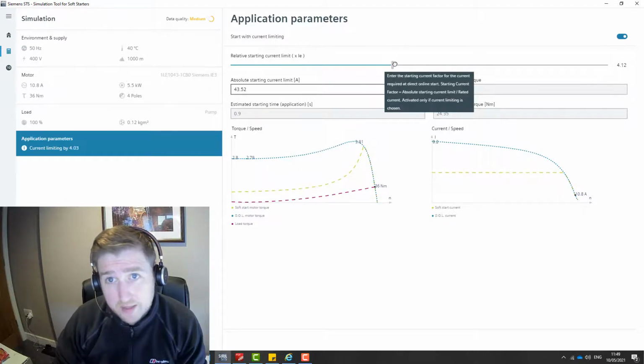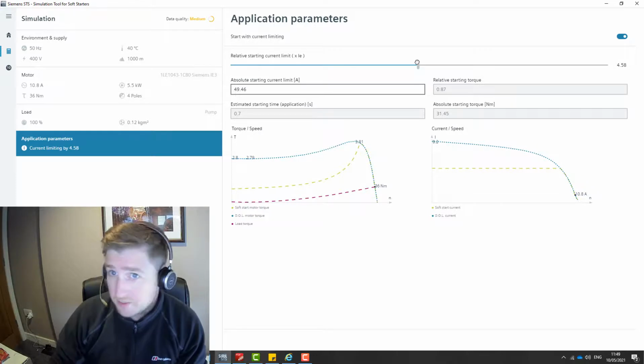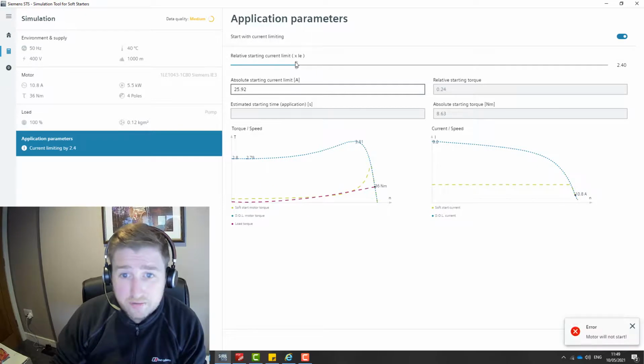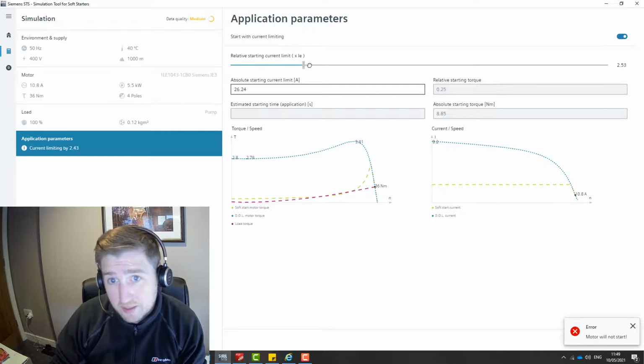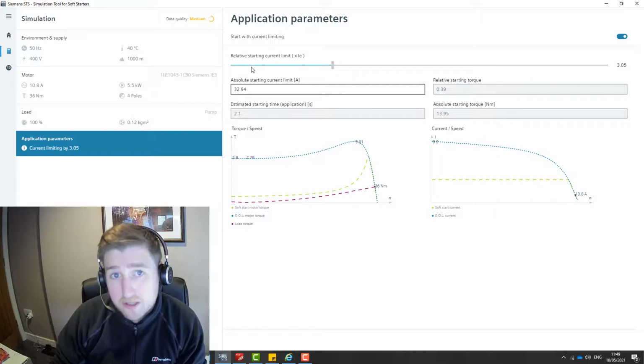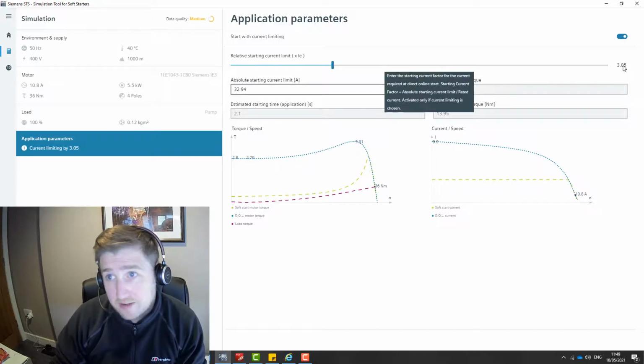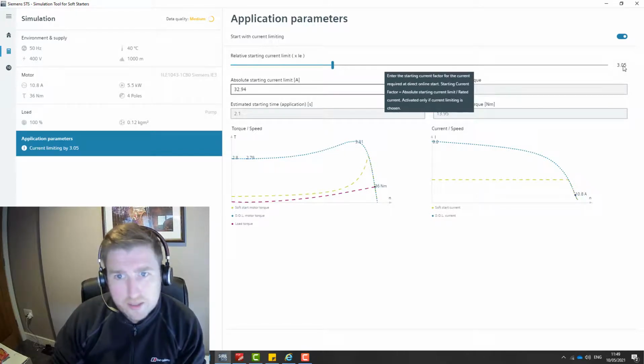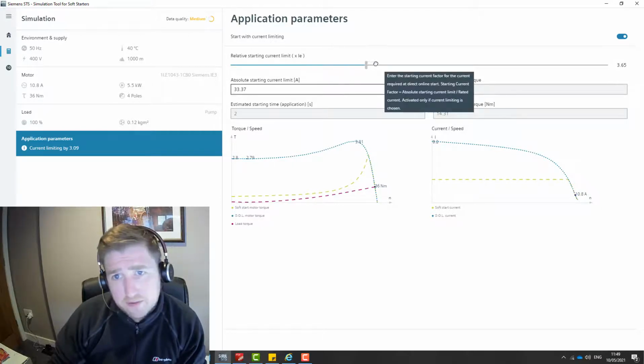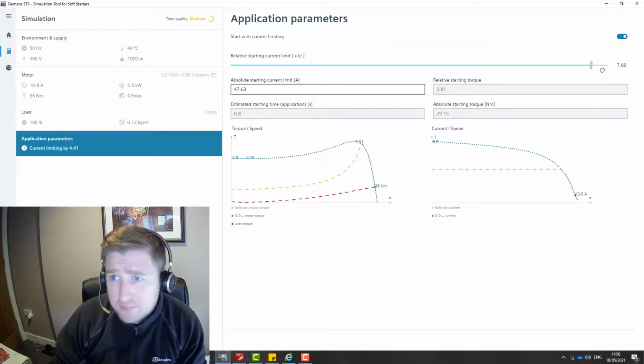So we can now gain an understanding of what we can set this current limit function to for it to be a successful startup of the motor. As you can see here, if we drop it too far, you'll get an error in this bottom corner which will tell you that the motor won't start. But then we can also increase it slightly, and now we know that we can set this starting current to 3 times the rated current, and that will start the motor successfully. We can up it even further if we want to not utilize that function to the maximum.